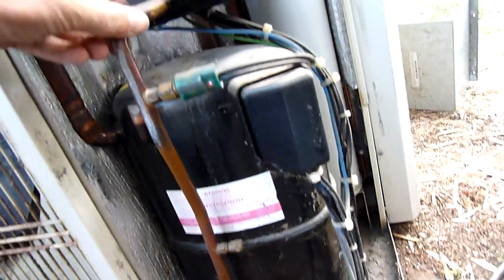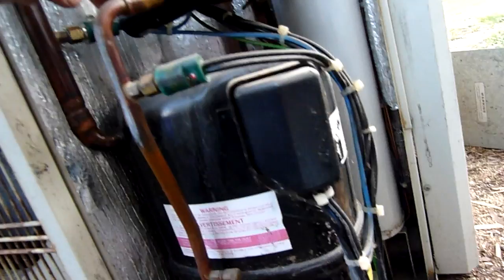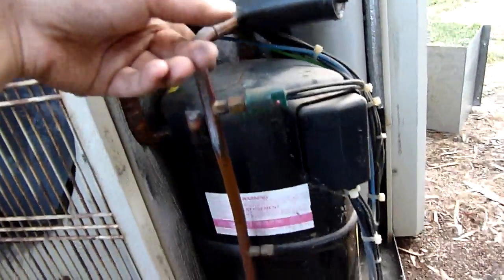That one's a little bit smaller than the other Carrier, smaller compressor, smaller accumulator. This one still works, I could plug it in and it'd work just fine, but on a hot day that condenser isn't going to be doing much condensing because even though it looks intact, it's severely corroded and blocked up. So it's junk — not worth trying to get a new condenser made for it.